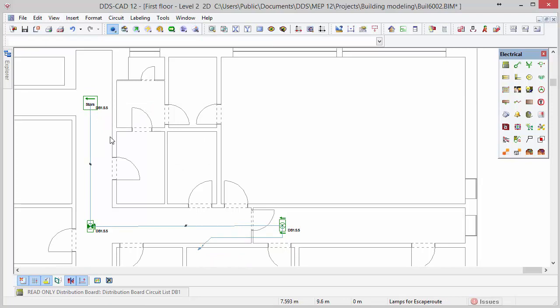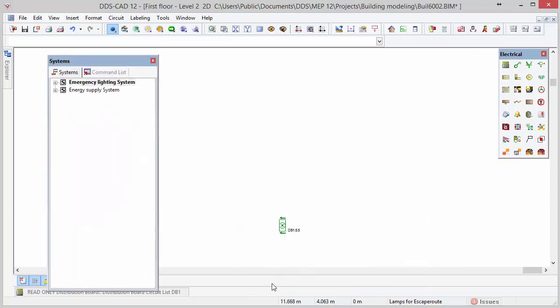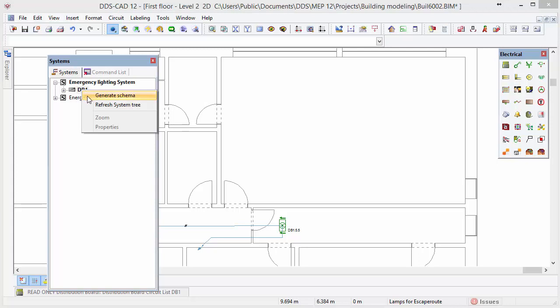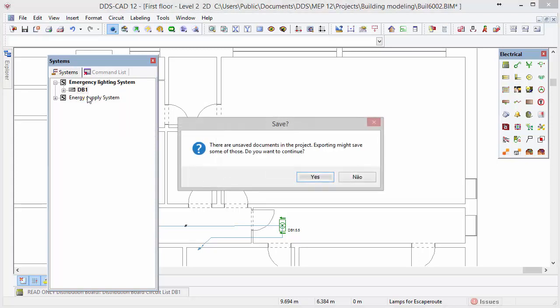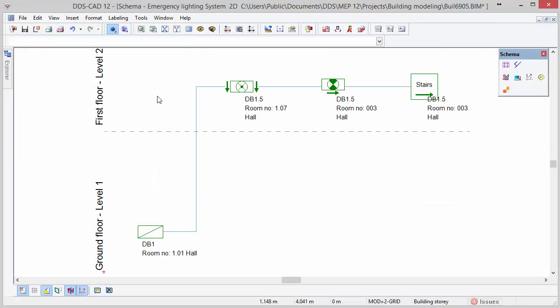DDS-CAD provides the possibility to create system diagrams automatically. To do so, activate the tab systems. Click to open the emergency lighting system tree, select the board and open the context menu with right mouse click. Select the option generate schema. Click yes to save unsaved documents in the project, then click OK to automatically create a system diagram. DDS-CAD automatically displays the diagram in which we see the lamps connected to the board with a reference to the story circuit and room.